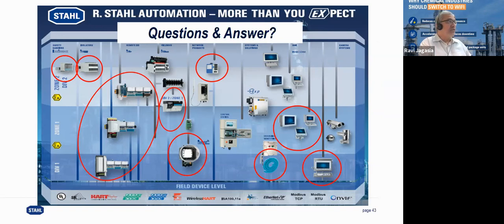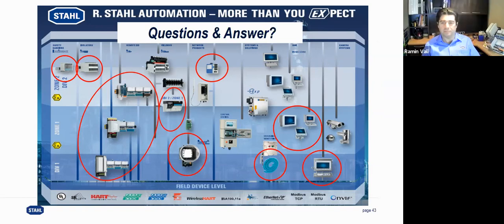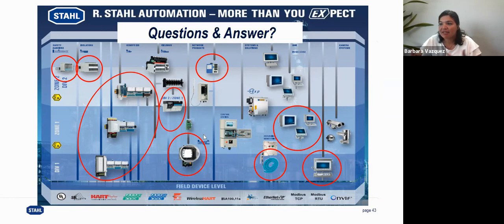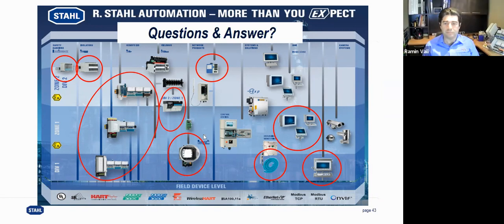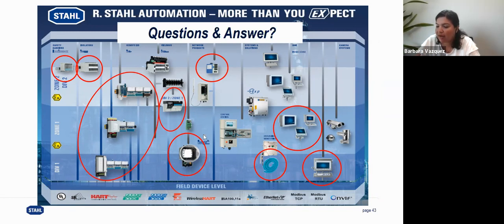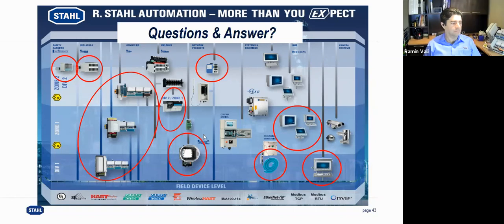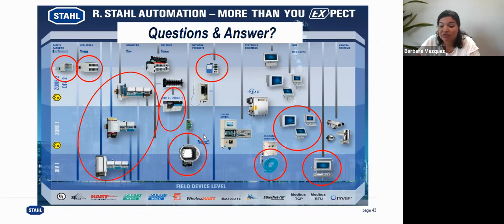The second question was, what if the voltage is greater, but the total energy is less? Barbara, you want to answer this? I believe it is for the intrinsic safety parameter. Yes, so it definitely depends how it was certified, right? When you have your intrinsically safe field device, the control drawing is what's going to define the rules to use that intrinsically safe field device in the area. So we need to match the entity parameters. Those values need to be covered by the IS barrier in the right way. We cannot go above those.